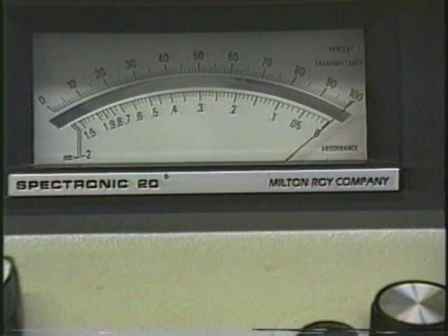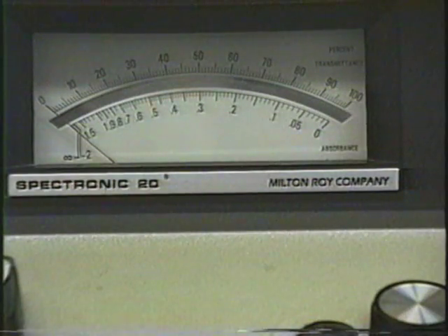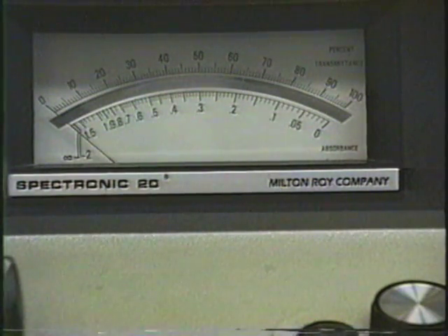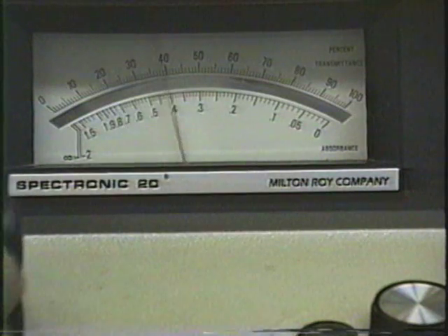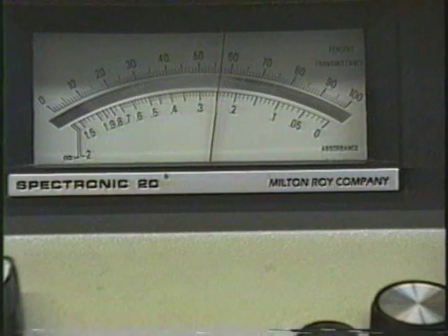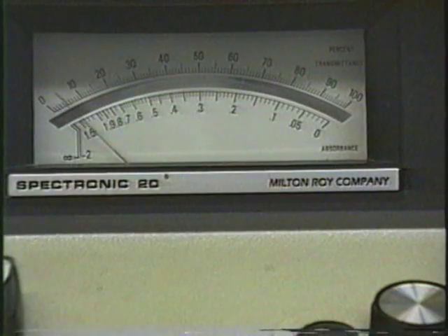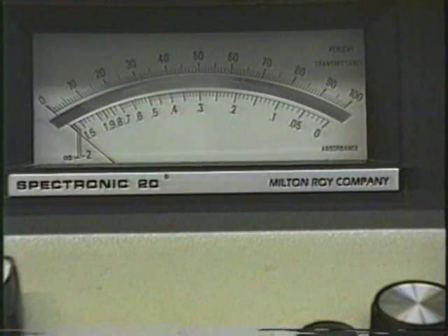There we go. Now the machine is set, back to 0. And again, line up the trademark with the mark on the sample holder and put in our sample. And now we read our sample. Our sample is reading 56.6 or 56.7. Well, it's drifting up a little bit. There will be a little drifting. That's why you read it twice in a row. Now, 56, we'll call that 56.8.